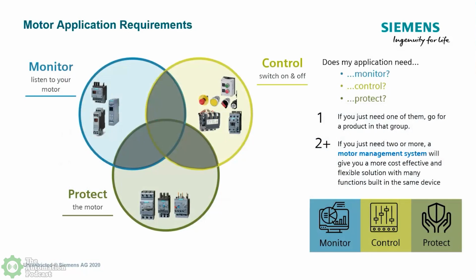But it will help you monitor. It'll monitor how many times the motor turned on, how many times it turned off. It'll give you up to 20 trips with a 21st being active, and it will time and date stamp them. So if you have an overload or phase loss or phase imbalance and so forth. And then it does all types of control. So again, we've partnered the SIMOCODEs with our soft starts before for some applications, and we've partnered them with our breakers, but for some very special applications. But the control part is mostly a starter, reversing or non-reversing application, or maybe even a 2-speed motor.